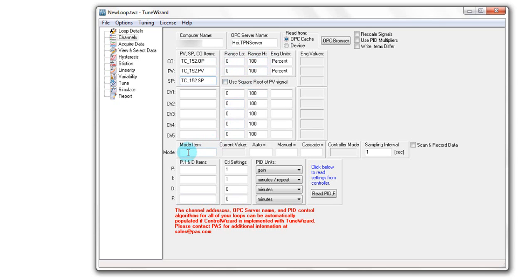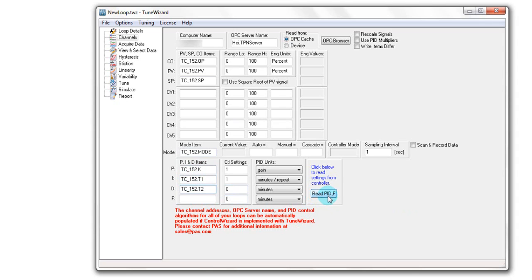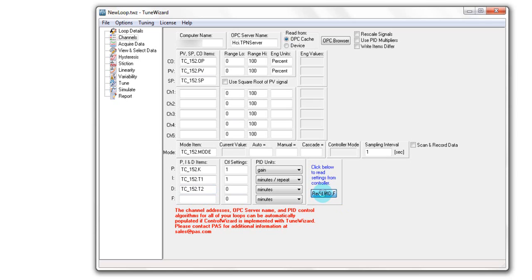I can define the parameter that brings in the mode of the controller and also the tuning constants. Clicking on this button, I can bring data in and make the connection through the connection that I have. So I can see that I have 0.5 for the proportional gain, 0.34 for the integral time, and 0 for the derivative time.